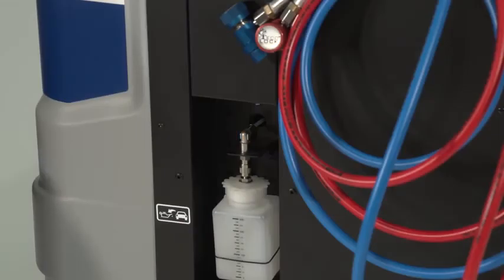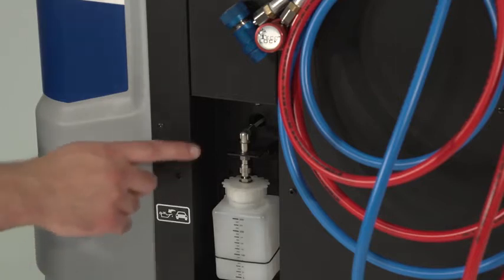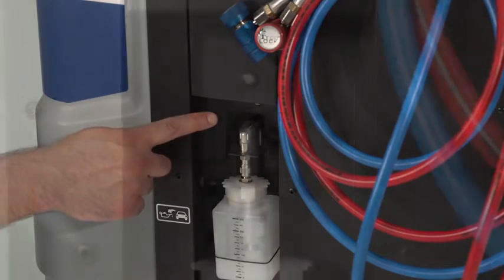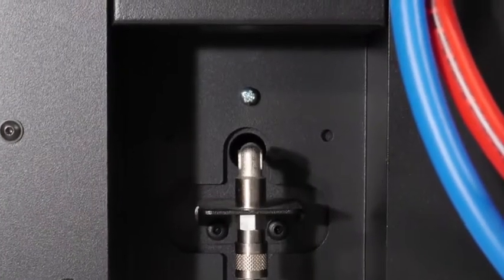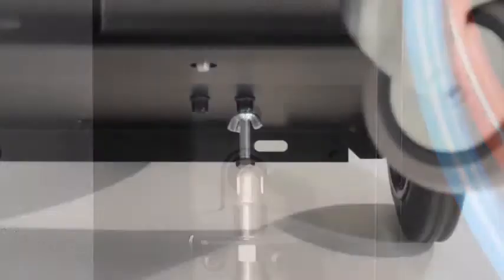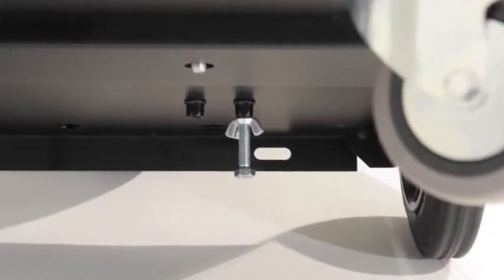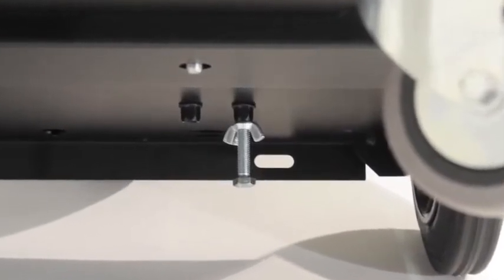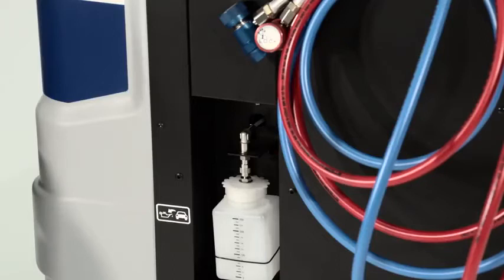The first thing you're going to do out of the box and off the pallet is remove the load cell set screws. The 1150 and 1150H have oil bottle load cells, and that set screw is just above the waste oil bottle. It is a chrome screw. You're going to remove that. And there's another set screw on the bottom of the machine for the refrigerant load cell. The 1120 only has the set screw for the refrigerant. There is not a load cell for the oil bottle on the 1120.